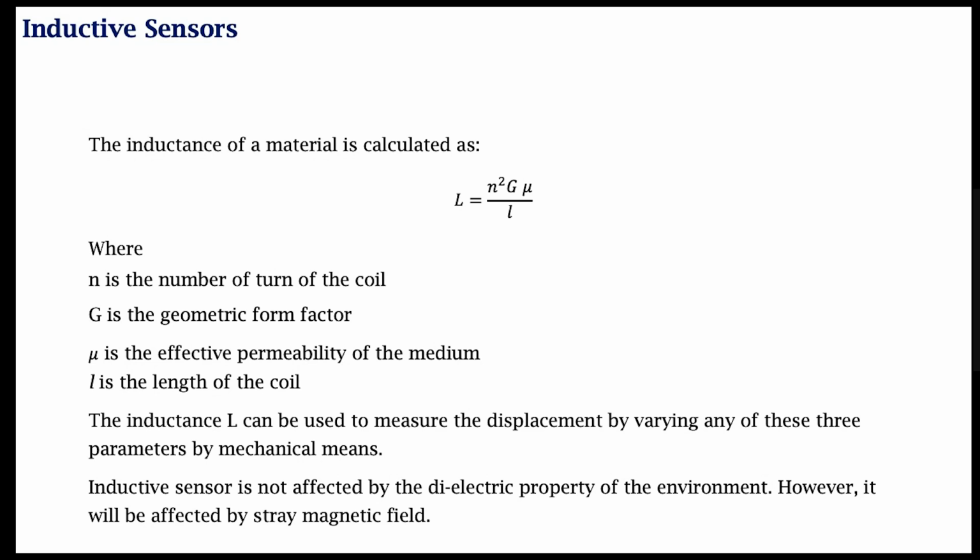Critically, note that these sensors are not affected by the dielectric or insulation or insulator property of the environment. Rather, they are affected by magnetic field, because these are coils wound around a core. They are affected by any stray magnetic fields.